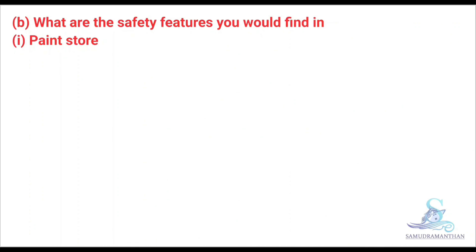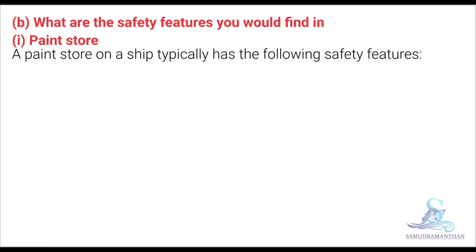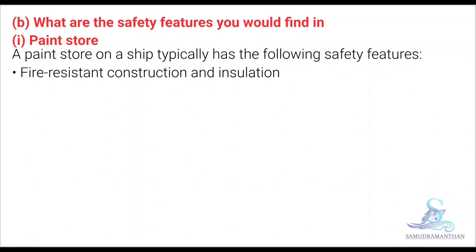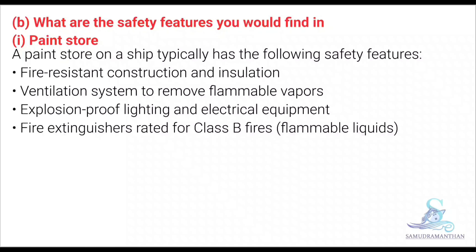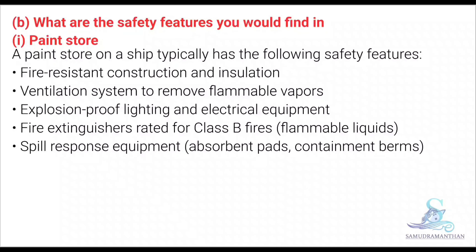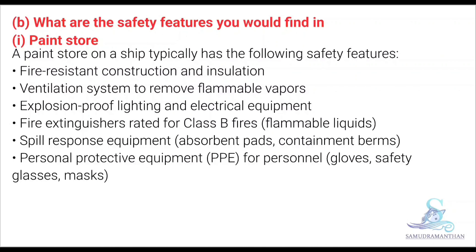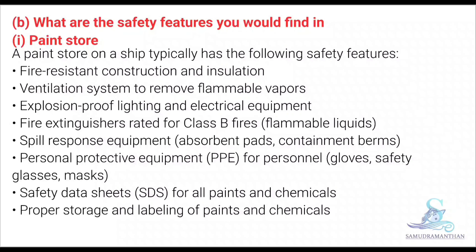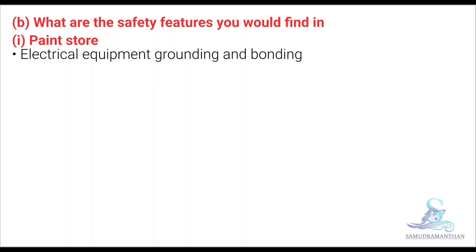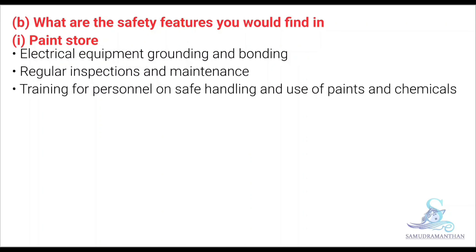Now we will move to the second part of the question: what are the safety features you would find in a paint store? A paint store on a ship typically has the following safety features: fire-resistant construction and insulation; ventilation system to remove flammable vapours; explosion-proof lighting and electrical equipment; fire extinguisher rated for class B fires (flammable liquids); spill response equipment including absorbent pads; personal protective equipment such as gloves, safety glasses, and mask; safety data sheets for all paints and chemicals; proper storage and labelling of paints and chemicals; electrical equipment grounding and bonding; regular inspection and maintenance; and training for personnel on safe handling and use of paints and chemicals.